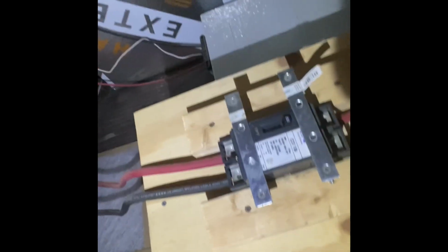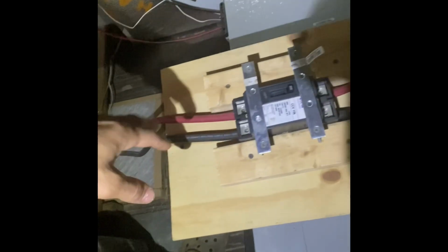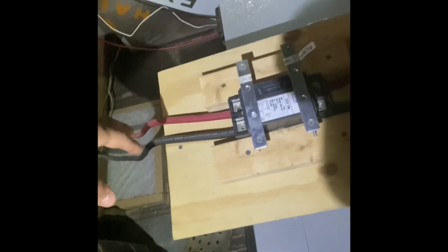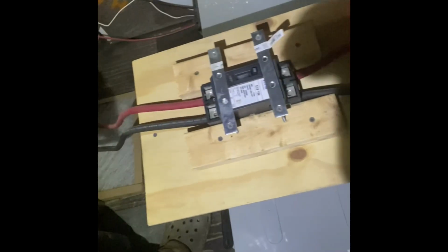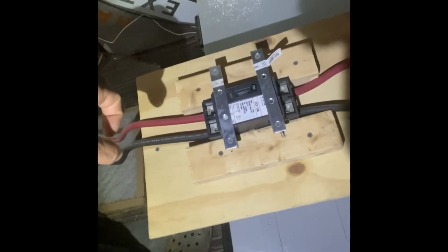600 volts, that's well over my capacity, so I'm on the safe side. Because I have it wired in parallel coming up to the inverter, I kept my outgoing amperage low and safe. So basically I didn't need to use the 4/0 wire, I can go as low as the 1/0. The 4/0 coating is a little bit thicker and more expensive, so save yourself the cost on that.